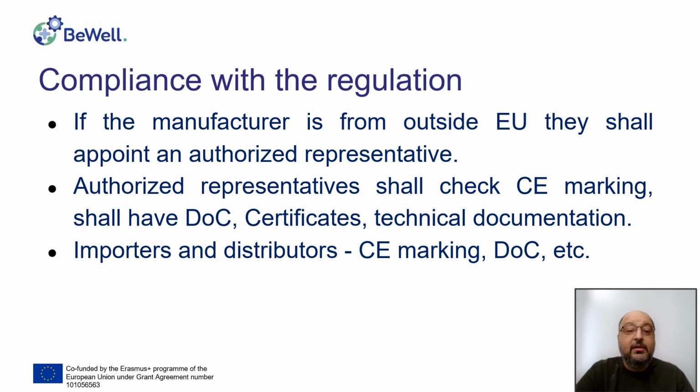Importers and distributors are also required to check the CE marking and the presence of a declaration of conformity, UDI registrations, and so on. The importer's name shall also be placed on the device or its packing.